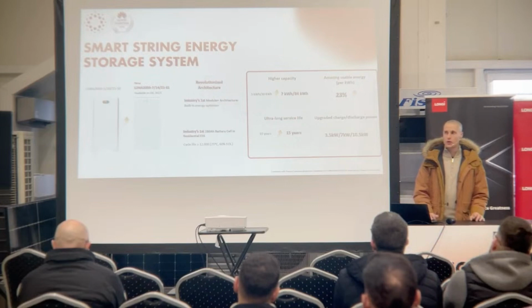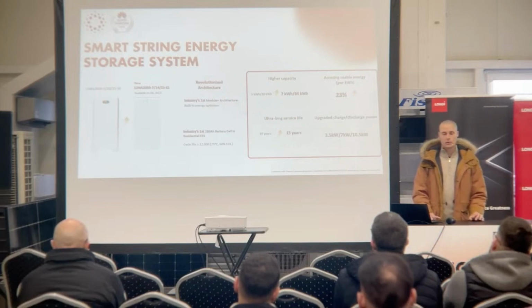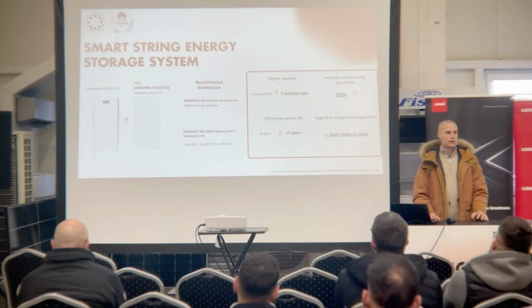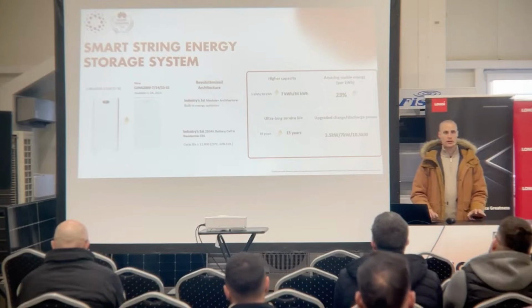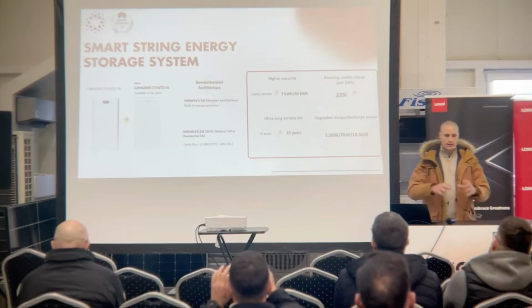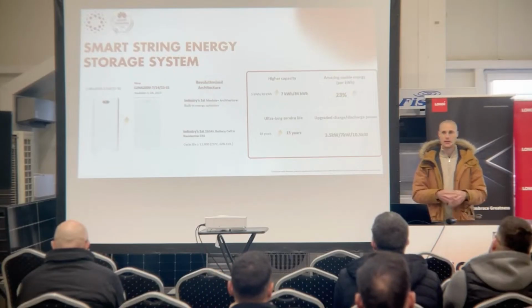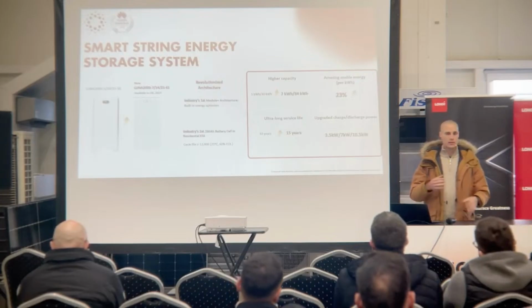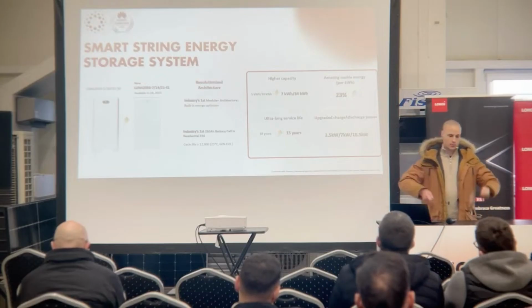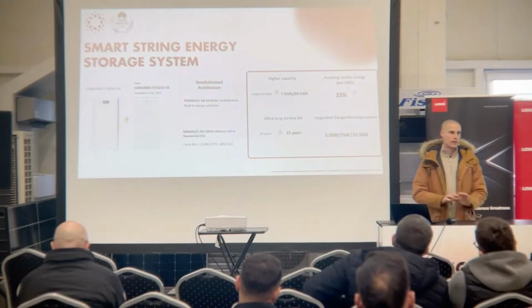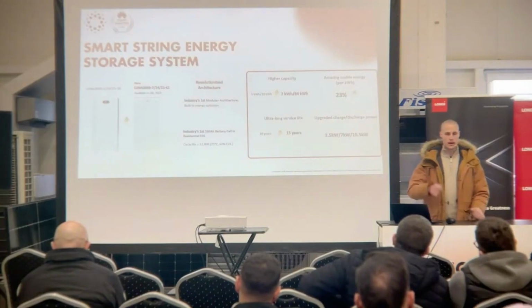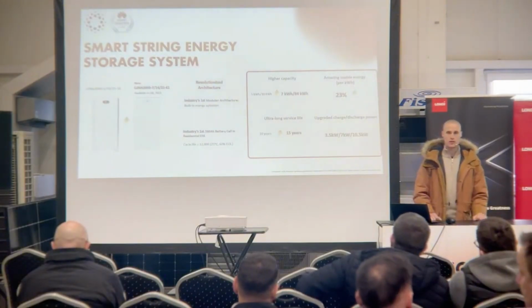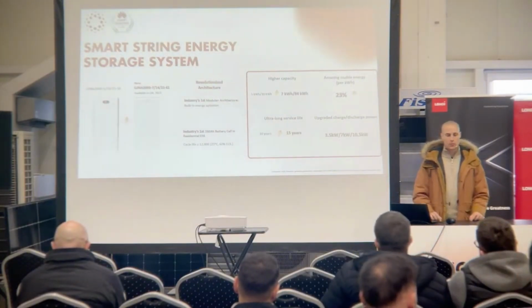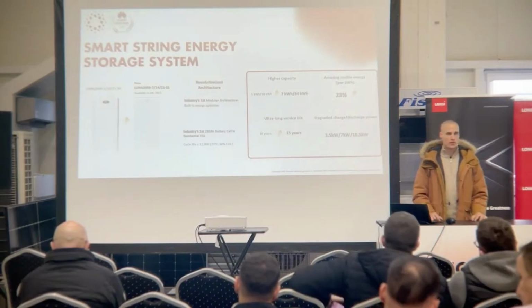I think the greatest advantage and the biggest improvement is that all of the DC and communication and earthing and everything connection is inside the housing. So basically, you don't have to connect anything between the battery packs. You just have to place the bottom of the batteries and put them on top of each other, and that's all. You don't need to do any kind of communication and DC connections on the sides. So it really speeds up the installation.